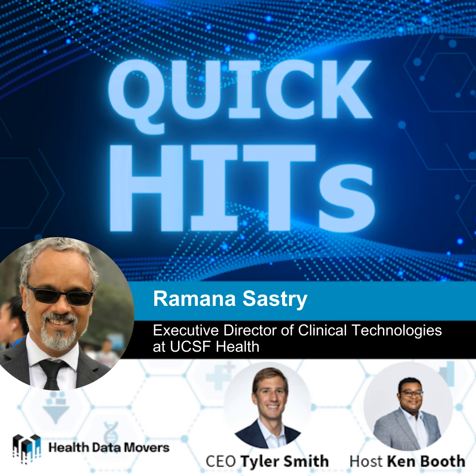A good example is a lab we have in one of our campuses, with an anesthesia machine set up. An anesthesia machine is pretty simple because it has a couple of different functions, but when you add things to it, or you want to trial something new, or even change something as simple as the location of the monitors, we have to bring in the anesthesiologist to make sure they're okay with that. Changing the location of a monitor can have a tremendous impact on their clinical workflow, because if the anesthesiologist has to turn their head in one direction when it needs to be turned in the other direction for proper clinical care, they're going to pick that up very quickly. So whatever configuration changes we make to medical devices, we do in conjunction with the clinicians so that it does not impact their workflows negatively.